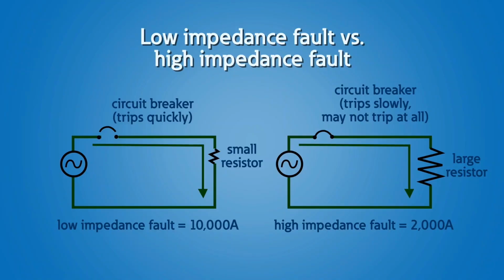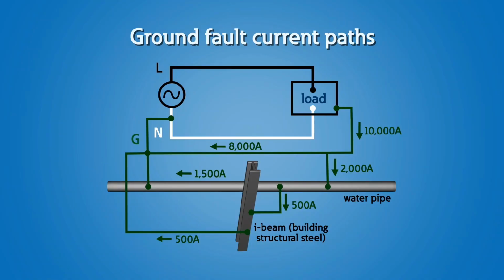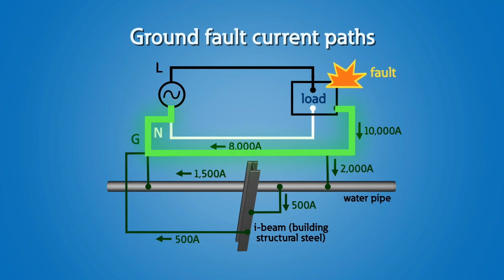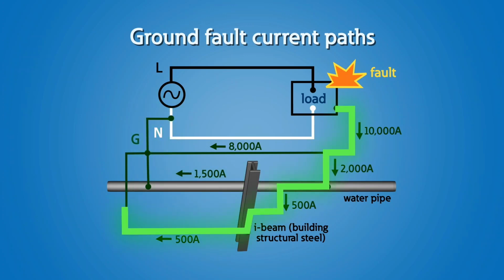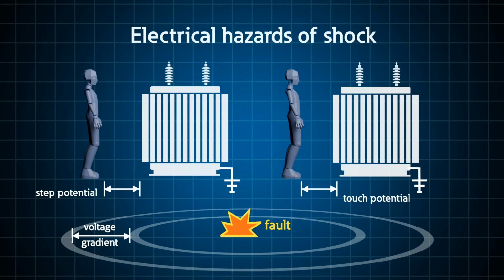Now, you want that impedance to be as low as possible because we want to drive the fault current as high as possible. We have to understand the basic principle that ground fault currents will flow anywhere they get a chance to. We're not going to guarantee that only the fault currents will flow through the equipment grounding conductor. And that's why we can't make the mistake of thinking that this grounding and this bonding will prevent someone from the electrical hazards of shock. When we talk about those electrical hazards of shock, we want to reduce our touch potentials or our step potentials. We want to keep everything at the same potential and be like that bird on a wire.